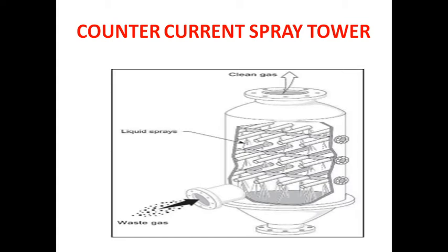Okay. So what about the gas velocity here? Gas velocity is very low. The range is 0.3 to 1.2 meters per second. This prevents excess droplets from being carried out of the tower. So due to low gas velocity, in the range of 0.3 to 1.2 meters per second, this tower must be larger than other types of scrubber to handle the same gas stream flow rate.